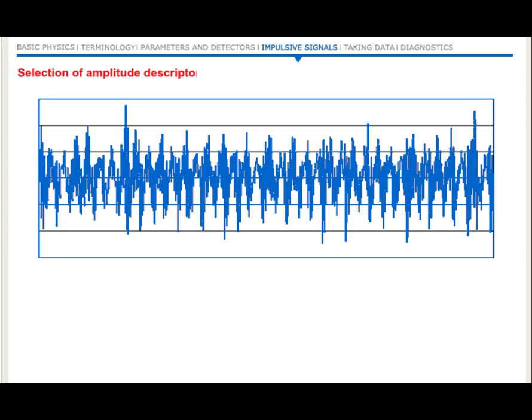Consider this signal's time waveform. It exhibits some tall peaks due to short duration impacts. Could these be the result of bearing defects? If we use an RMS amplitude descriptor to arrive at an overall value for this signal, then the effect is to average the individual values and reduce the measured level to a much lower calculated value. Individual peaks would have to grow massively before they had an impact on the RMS value.